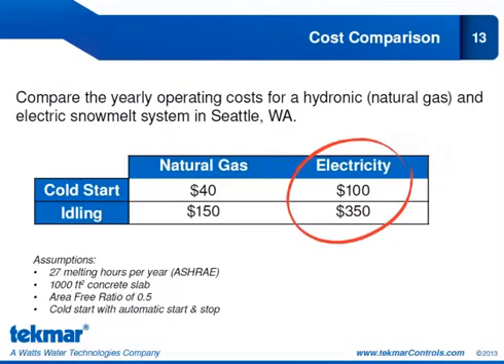For a second comparison, in Seattle, Washington, ASHRAE shows only 27 melting hours per year. Even though natural gas is still cheaper — $40 versus $100 for electricity on a cold start — because the overall cost to operate with electricity is so low, you're probably not going to see the return on investment needed to justify a hydronic system. In a low-melting-hours climate like Seattle, an electric snow melt system would likely be the better choice.